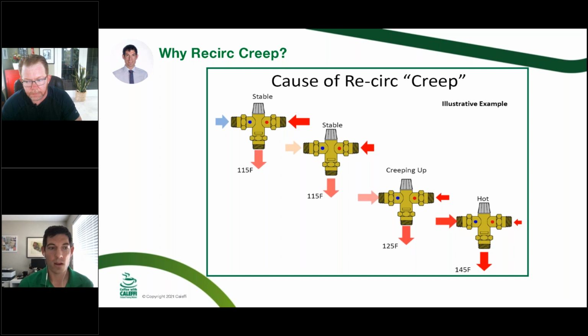So at that point, we have exceeded our set point because we don't have anything cold to mix the hot with, and that's when that first person getting up to turn on a fixture in the morning could get a blast of hot water, and then it goes away. So it's kind of a tricky symptom, because then as soon as somebody takes a shower and hopefully they don't get burnt, it's going to go back to that far left stable condition again.